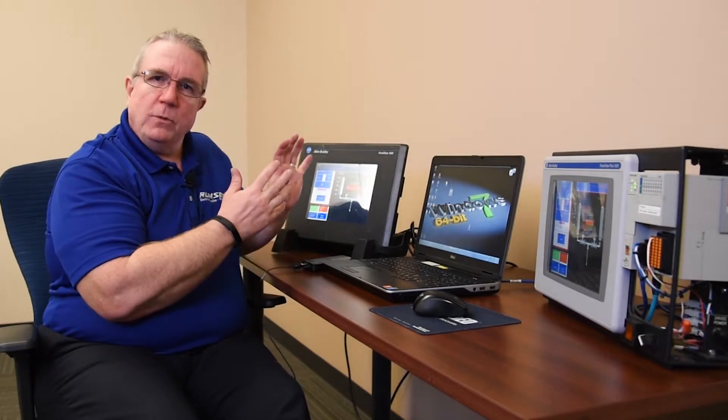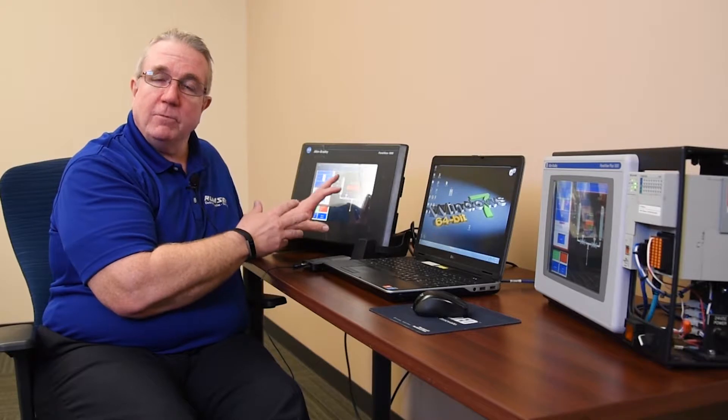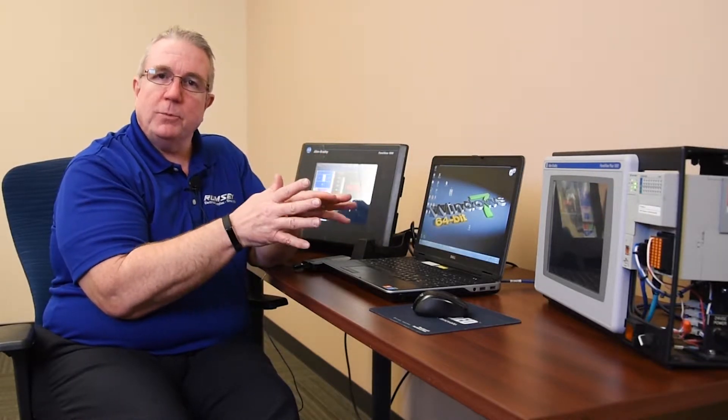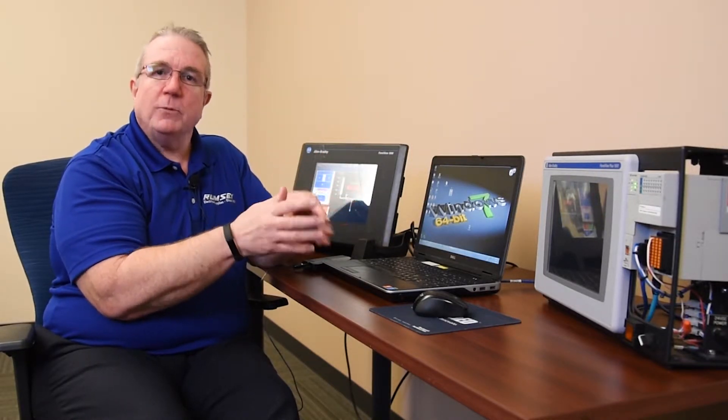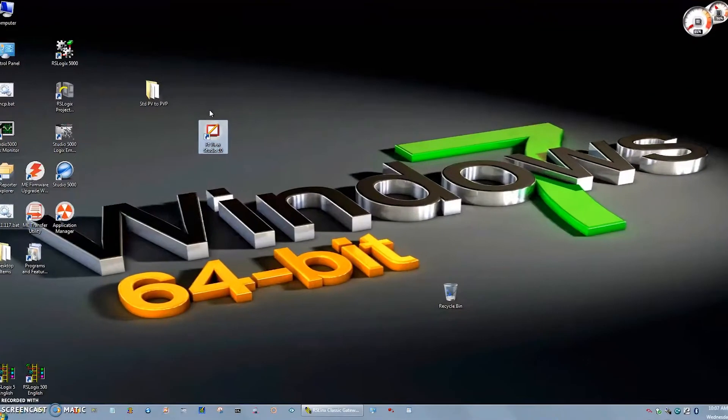One thing to keep in mind with any migration, going from old to new, is you have to be fully familiar with the project before you start. You have to know if it has any bugs or at least the full operation of the PanelView that's currently running before you go into the new product. If you don't, you might waste time trying to correct the problem in the new product when it was already in the original product to begin with. So let's look at the computer and the software itself.